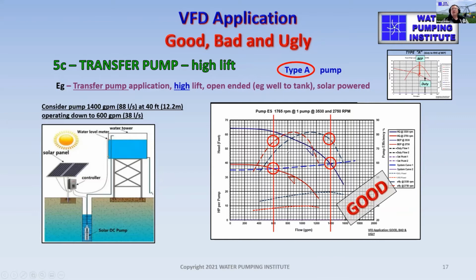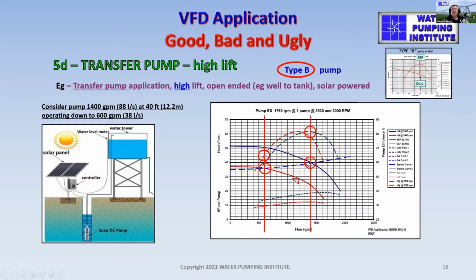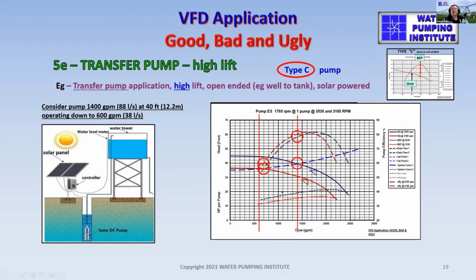But what if we were to look at a type B pump for this application, where we start off with a pump at best efficiency point at the duty point? Well, it works fine at the peak duty, but when you slow it down, the efficiency drops right off from 82% down to 67%. So that's not particularly flash. I'd call that bad. But even worse, what if we went for a type C pump, where the duty was to the left side of the BEP?